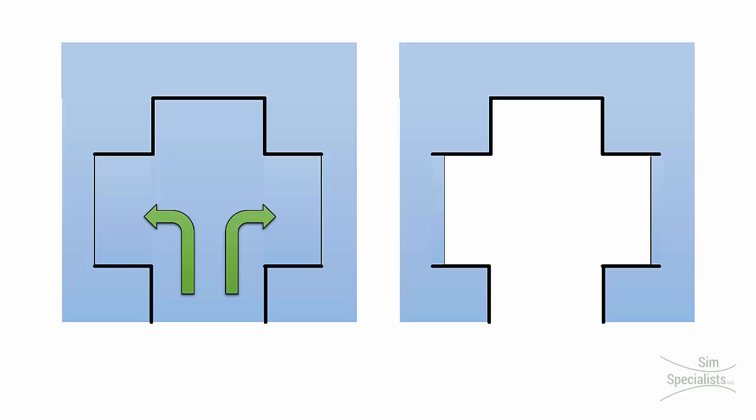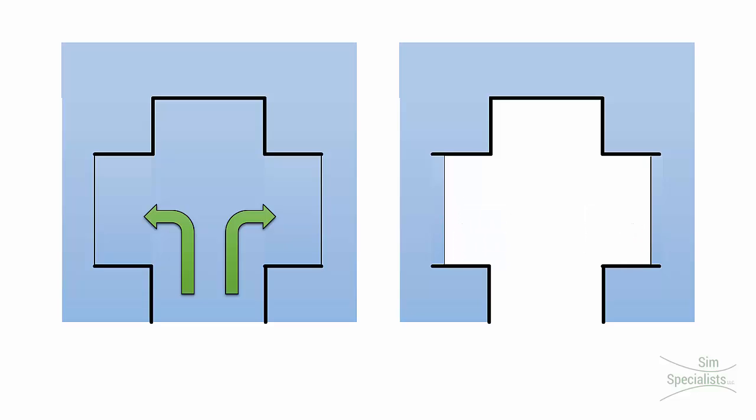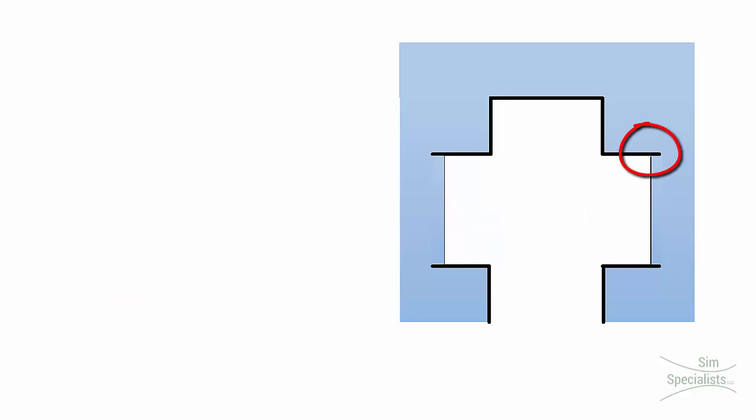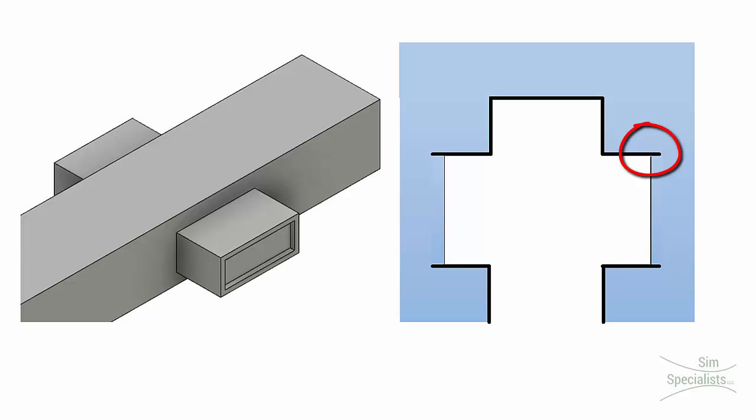When suppressing the ducting, the air inside the ducts is eliminated and flow boundary conditions are assigned to each of the supply locations. Note that a short indent is created in CAD on the duct volume to assign the flow boundary condition to a unique surface.